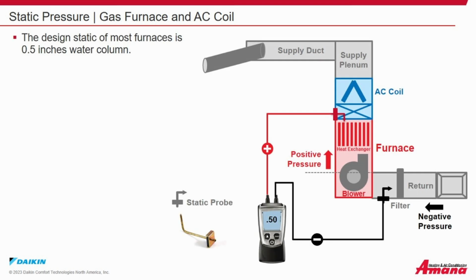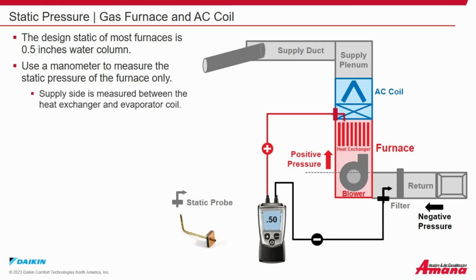Static pressure, gas furnace, and AC coil. The design static of most furnaces is 1/2 inch water column. Use a manometer to measure the static pressure of the furnace only. Supply side is measured between the heat exchanger and the evaporator coil. The return side is measured between the blower wheel and the filter.